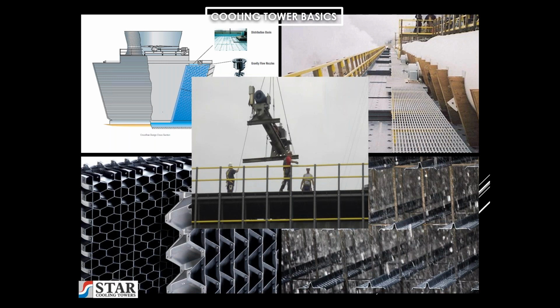Due to tremendous torsional forces of a large fan and high horsepower, unitized steel mechanical supports are needed to provide a constant plane relationship between the motor and the gear reducer. And this is true in both cross-flow and counterflow. These supports can be steel and I-beam and plate, or it can be I-beam or channel, depending on the size of the fan and the horsepower.